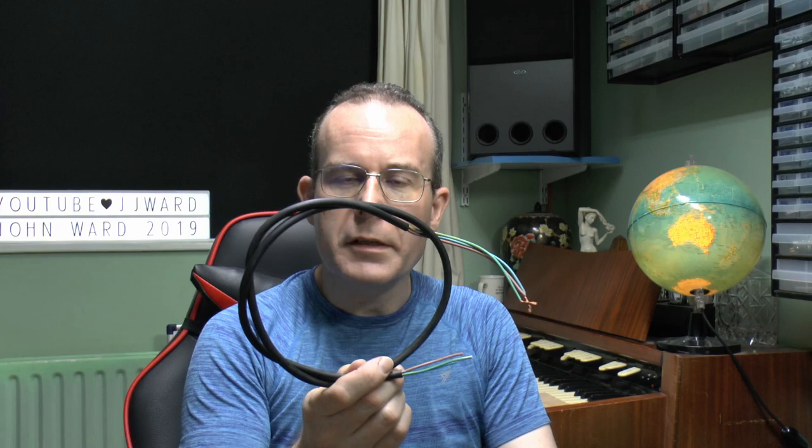Now, this came from an outside light. It's one of those jobs that you sort of just spike into the ground and have the flex going off to some junction box. Obviously you can then move it about and direct it at whatever things you want. This has been outside for a number of years, and the reason we had to go there was because the entire circuit was testing as faulty, and it turned out that the cable itself was at least one of the faults.